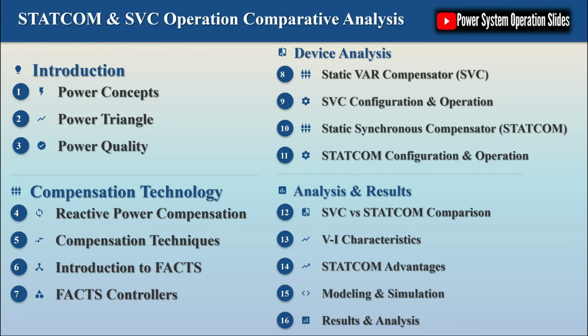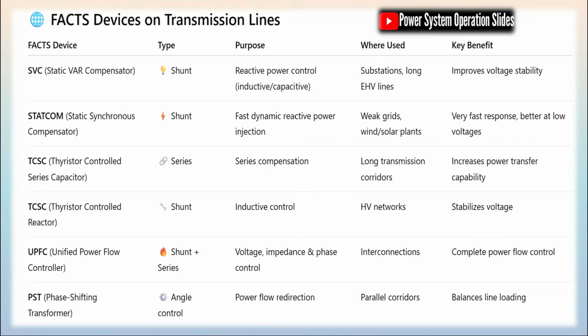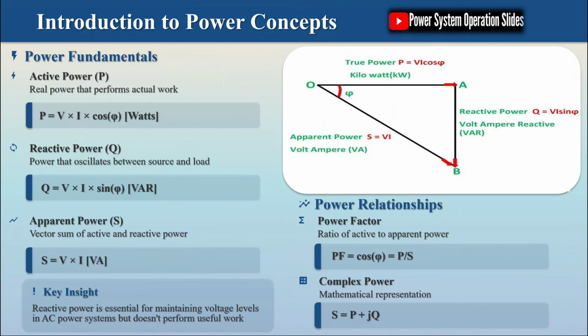Flexible AC transmission systems, FACTS, represent a revolutionary approach to enhancing the controllability and power transfer capability of AC transmission systems. FACTS devices are power electronic-based systems that provide control of one or more AC transmission system parameters. These devices can be classified into two generations. First-generation devices like static VAR compensators, SVCs, and second-generation devices like static synchronous compensators, STATCOMs. Both SVC and STATCOM are shunt-connected FACTS controllers designed to provide reactive power support to improve voltage regulation and system stability.